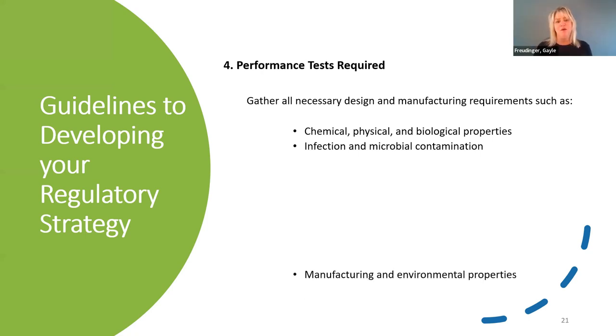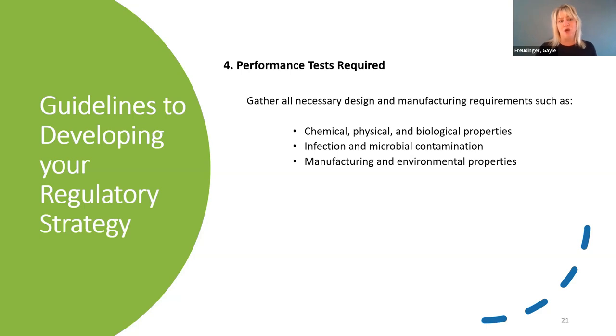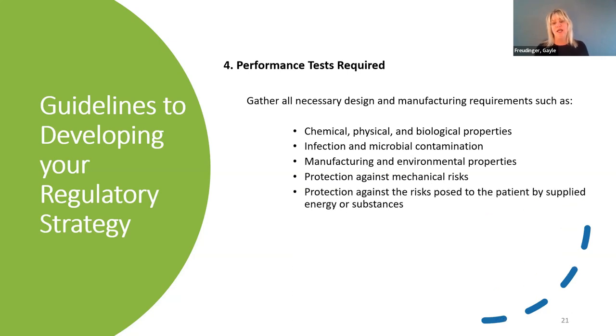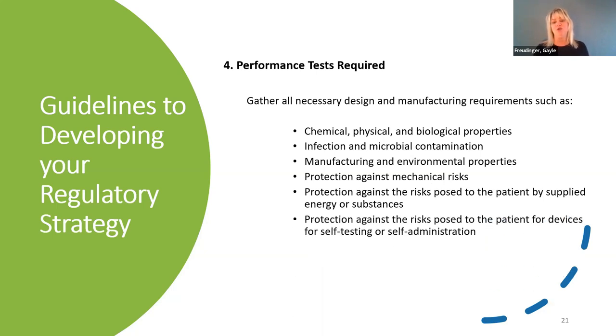Great, thank you. The manufacturing environmental properties are also important performance tests. Any mechanical risks. So again, as your device has higher risk, you're going to have to test for those risks. Protection against risk posed to the patient, by any supplied energy or substances in the device. And protection against the risk posed to the patient for devices for self-testing or self-administration. You know, perhaps it's a device that is a sling or something for your arm, and it uses some type of electric current, and that patient goes into the shower. You know, that could be a risk or a danger.